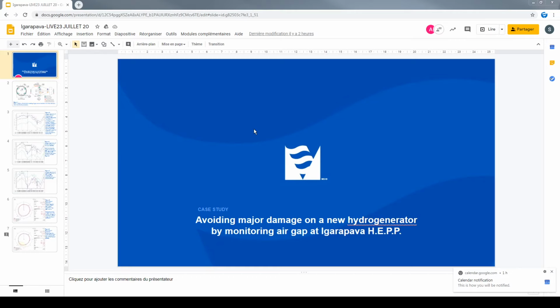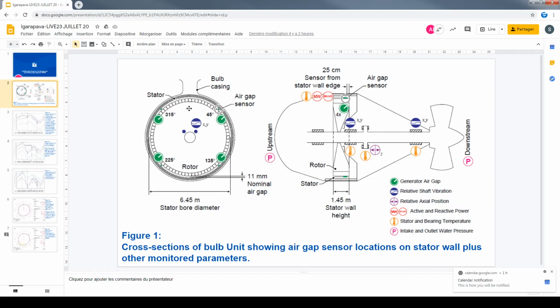Let's take the mouse here. Okay. As you can see, it's a horizontal unit. It's a fairly small unit, and it's very slow speed. And in this case, we installed 4 air gap sensors at 90-degree intervals, but with a slight offset of 45 degrees, which is what we usually do for horizontal units to get better coverage. They also had some shaft vibration probes and some temperature probes and some pressure probes.